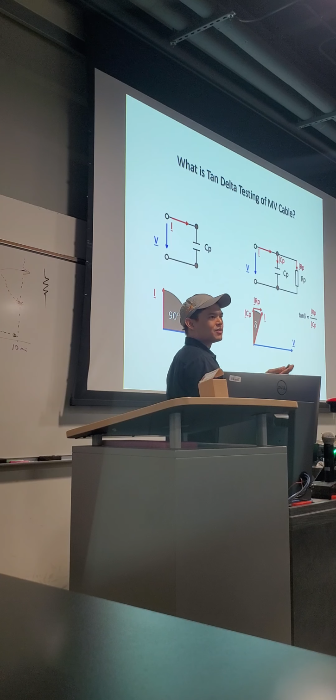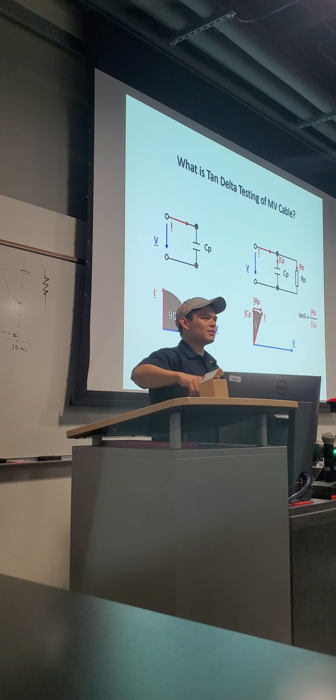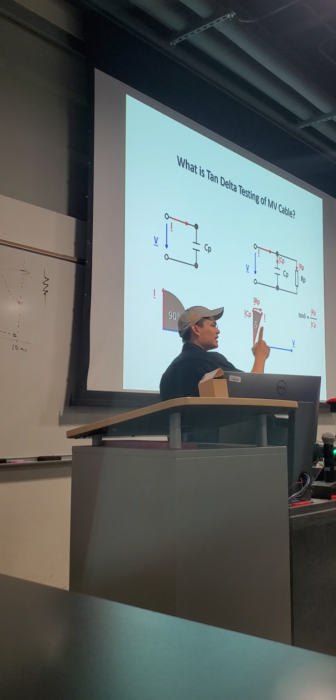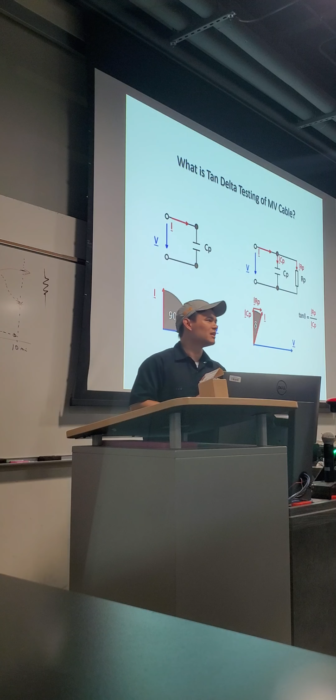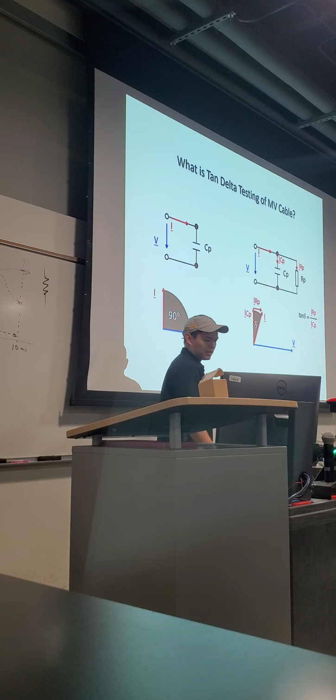And the nice thing is you're familiar with DC high pots, but instead of direct current being applied, it's going to high pot, overstress it, over a long period of time, like a long sine wave. And again, the idea being that it will be non-destructive. That is the viable alternative to high potting service-aged cable, which is the one takeaway from this class. Do not DC high pot service-aged cable. But VLF provides that alternative. So excellent question.